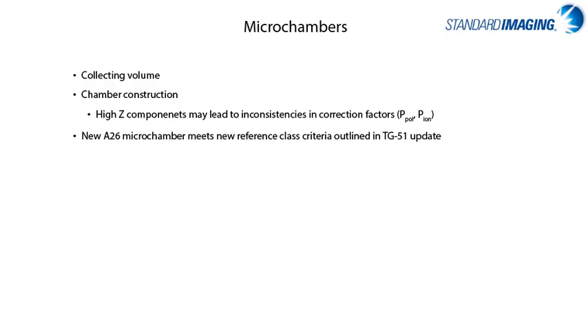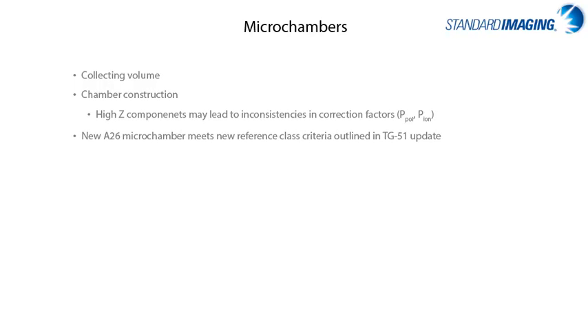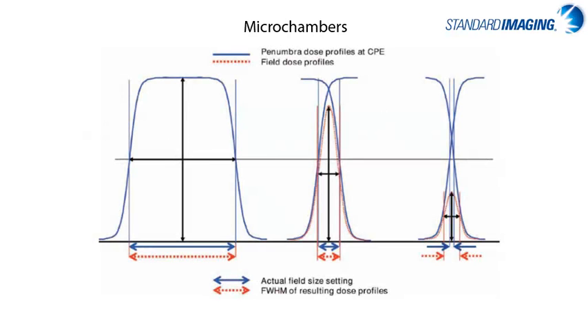the A26 can be used in very small fields for reference-type measurements. However, I will note that your exact numbers for something like an output factor may or may not agree with your neighbors due to the numerous sources of uncertainty with small fields as we've talked about, and the non-uniform characteristics of these fields makes comparisons across institutions, or even within institutions, difficult.